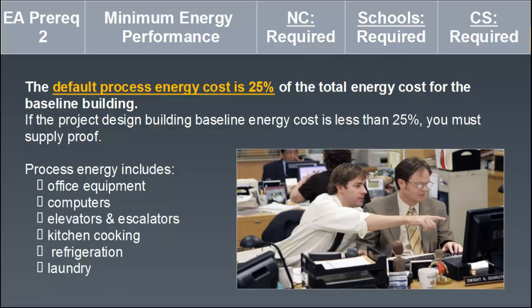For buildings such as industrial manufacturing buildings, you may want to incorporate process load in its actual amounts because it is the majority of your energy use. You need to carefully go through the process of setting those baselines based on national standards. It's important to discuss in early design for those types of buildings, and there are more case studies coming up. At EcoReal, we're currently working on a brewery and a plastics manufacturing company, and for each one we're having to assess the individual equipment with the team to come up with those baselines beyond ASHRAE 90.1.